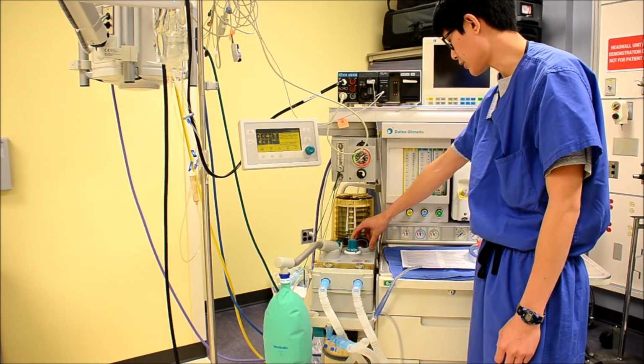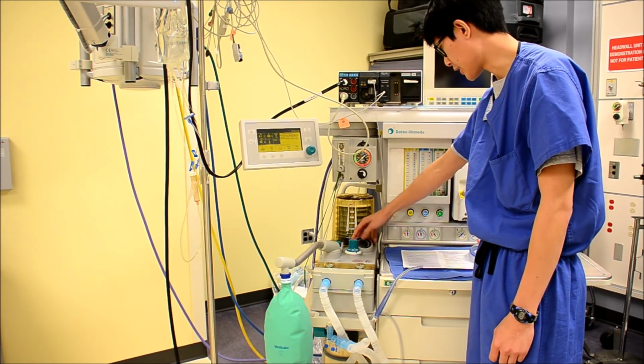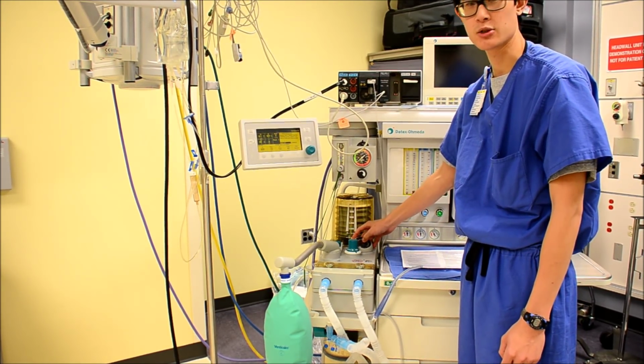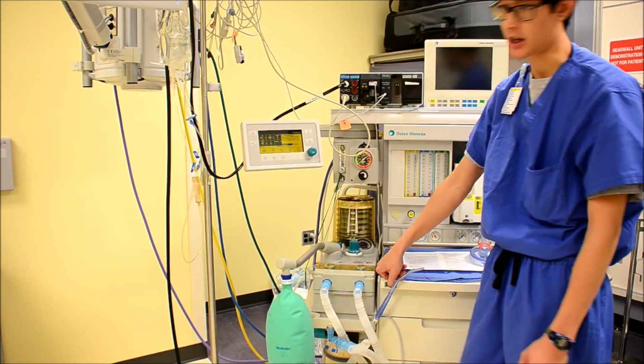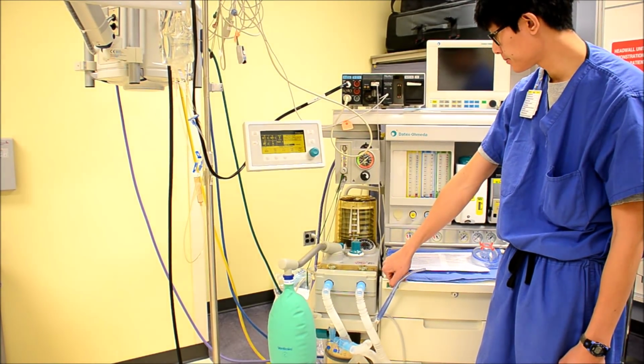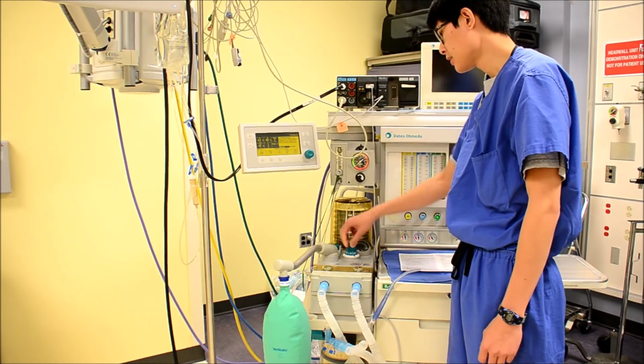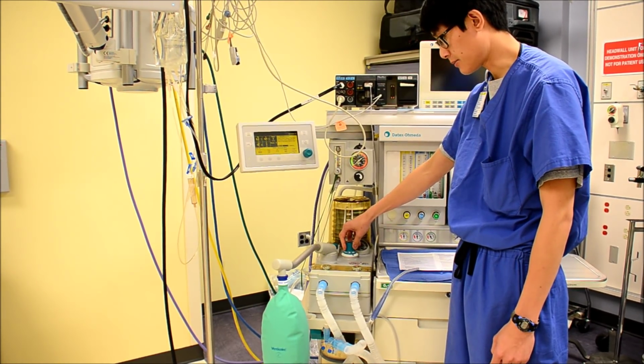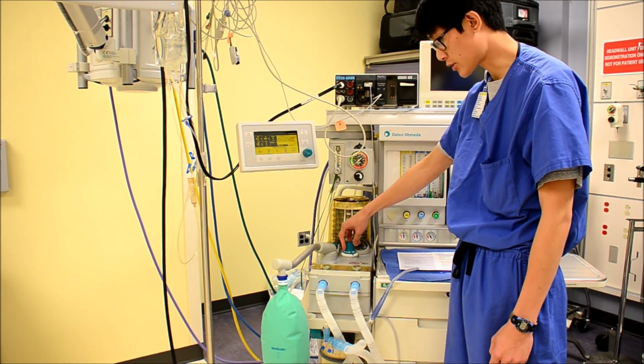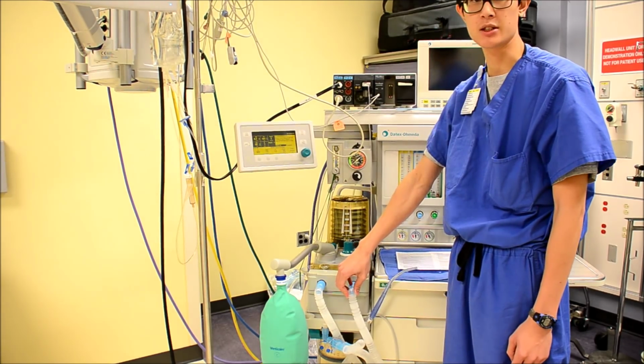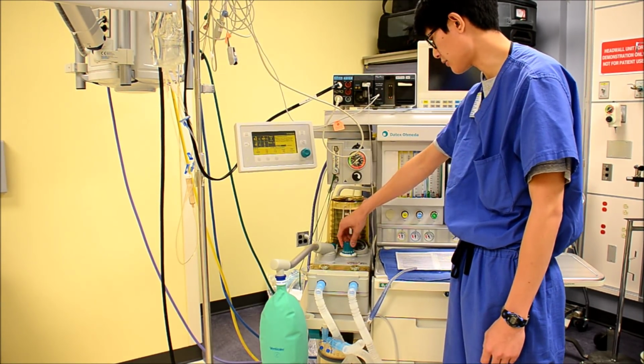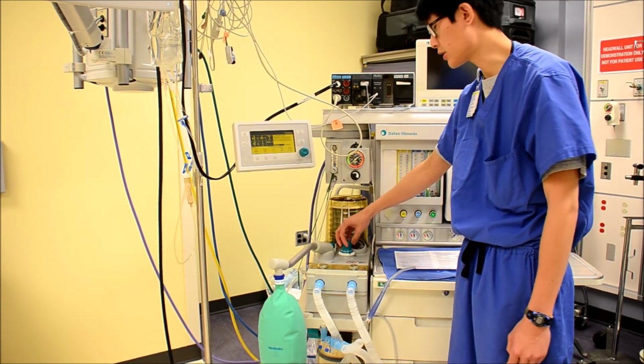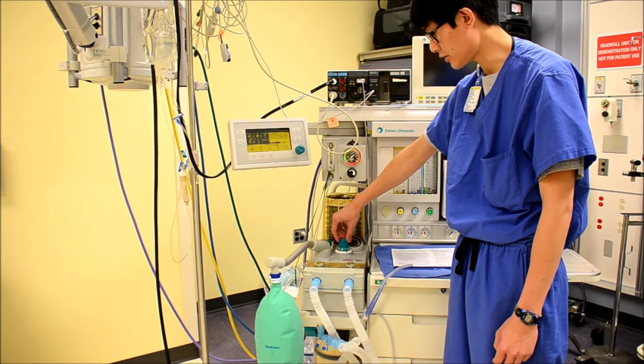The pressure on your gauge should never go above 10 centimeters of water pressure when the APL valve is open. Yeah, I can see that now. The next would be to make sure your circuit will pressurize. That's to make sure there's no leaks in the system. So you'll turn your APL valve all the way to 70, and you can tell that as you get closer to 70, you can hear it click.